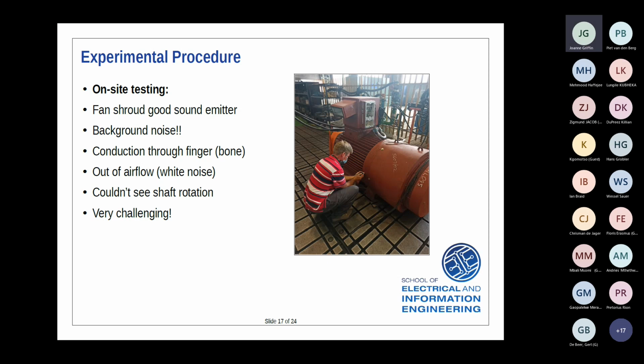The fundamental problem I had here is that from this position at the back of the shaft, I couldn't see the front, the rotating end, so I didn't know exactly when the shaft started. That was quite problematic, because the run-up test took a minute or two, and it slows down so gradually that it goes completely quiet - you can't feel any vibrations, and with so much background noise in the factory, you don't know when the machine has actually stopped. In hindsight, it would have been better to try to at least peer around the corner to see what was happening on the shaft end, though it was covered by a protection shield anyway, so it was very difficult.